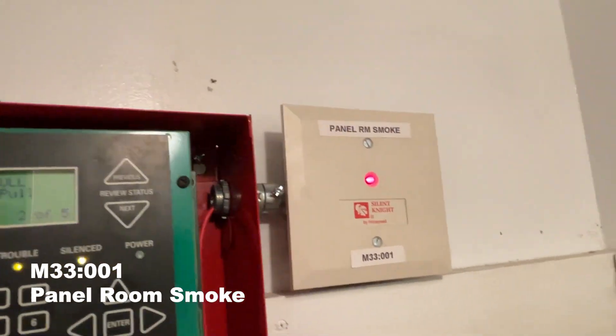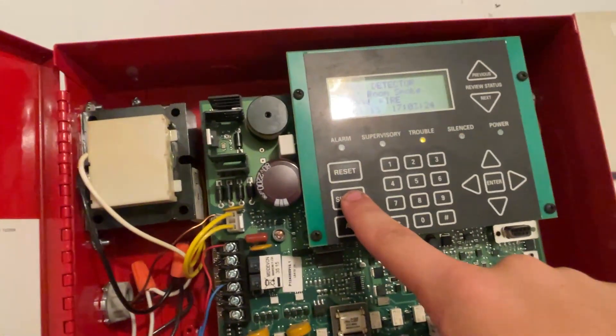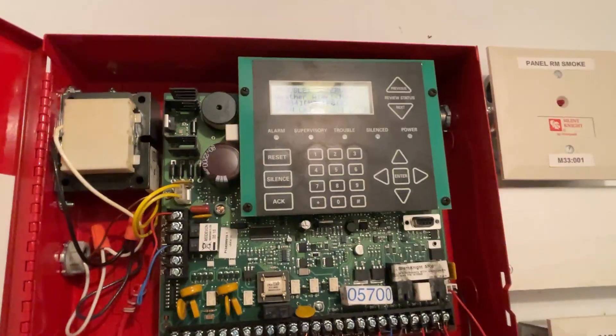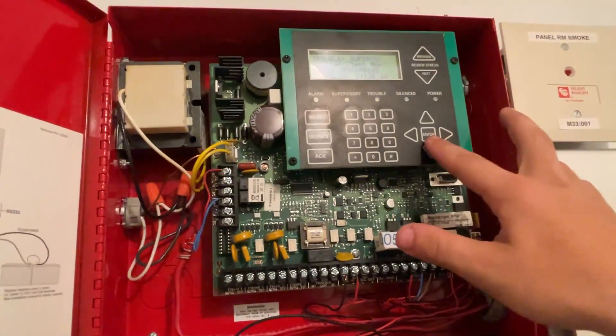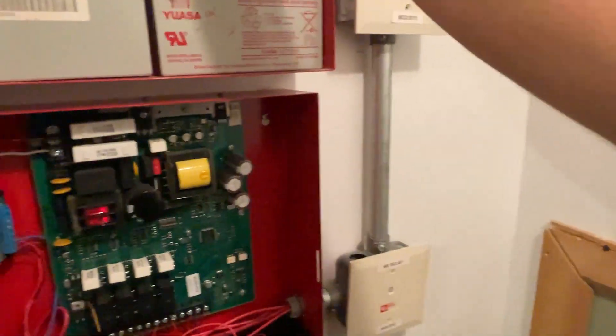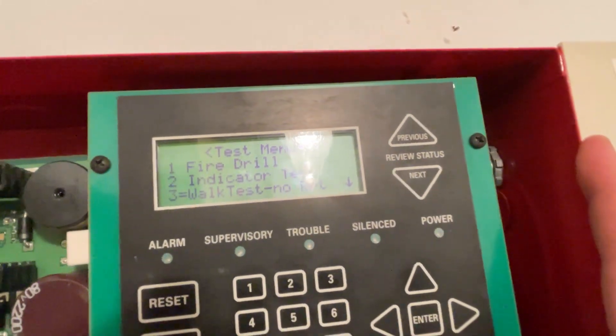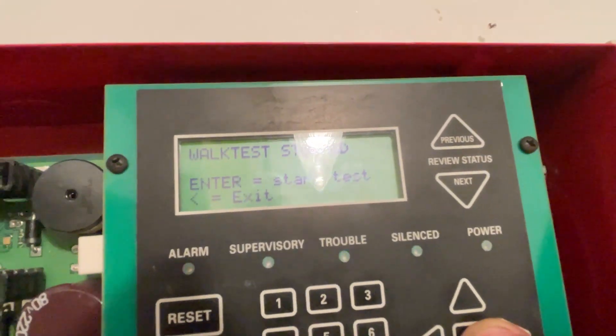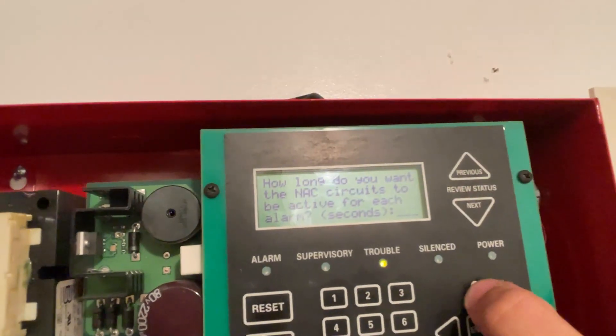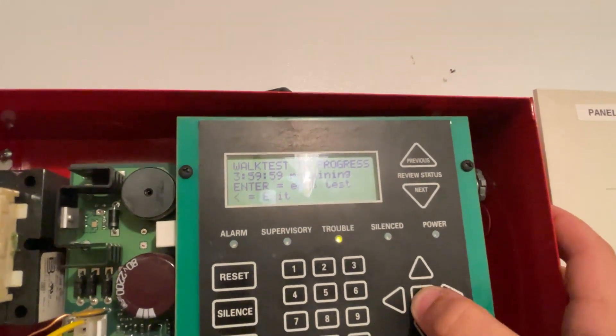Next is the panel smoke, which will activate the monitor module. Now we're going to put the system in walk test. To enter walk test, enter the menu by typing in your six-digit code, then go down to system tests, then walk test. In this case, no I/O. We start walk test and set how long we want devices to sound — let's say eight seconds. The system is now in walk test for four hours.